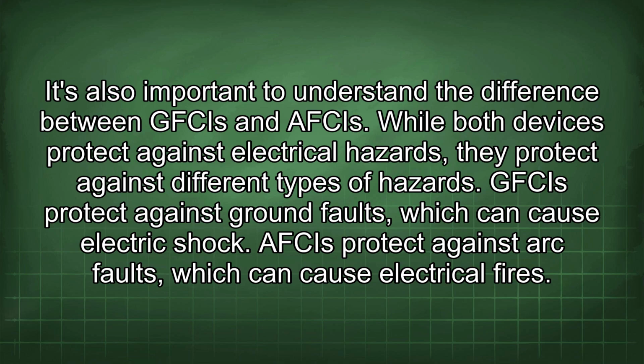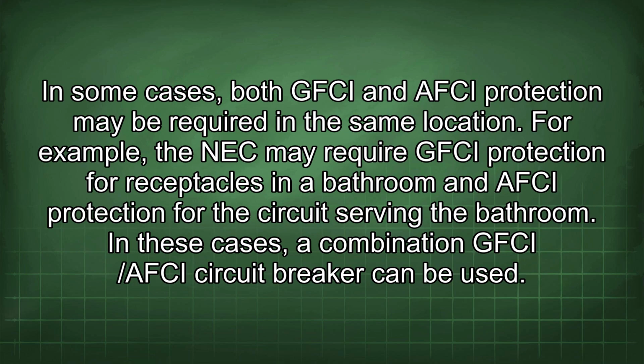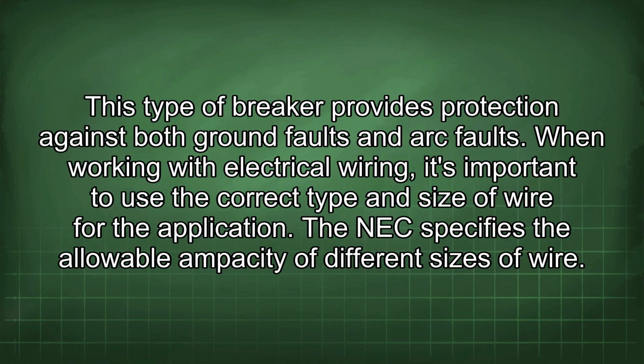AFCIs protect against arc faults, which can cause electrical fires. In some cases, both GFCI and AFCI protection may be required in the same location. For example, the NEC may require GFCI protection for receptacles in a bathroom and AFCI protection for the circuit serving the bathroom. In these cases, a combination GFCI/SI circuit breaker can be used. This type of breaker provides protection against both ground faults and arc faults.